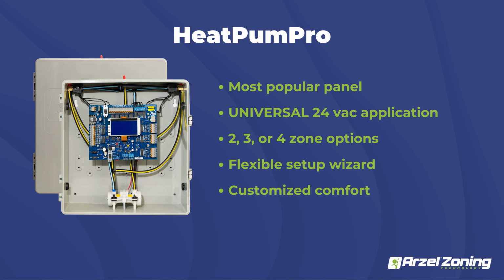It's also going to handle any kind of changeovers you guys would have. So if you guys are doing a dual fuel system, you'll also program that in. And once that temperature is reached, it's going to flip over to your auxiliary heat source and run that as well. It also has all of your controls built in. If you had like electric backup, it's going to have your electric heat resistance lockouts. So if you guys wanted to do a hard lockout on the electric backup heat and you didn't want it to engage until a certain temperature outside, all of that is included and built into the panel.